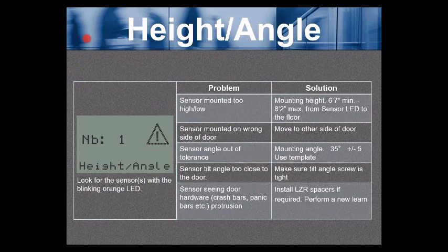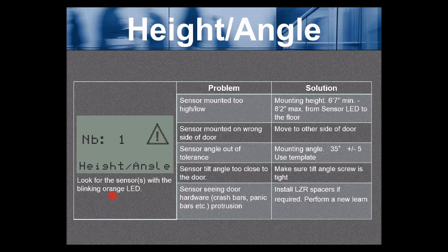Height angle error. Again, look for the sensor or sensors with the blinking orange LED. The problem for the height angle error, the sensor is mounted too high or too low. That's probably the number one cause of a height angle error. The mounting height is 6'7" minimum to 8'2" maximum from the sensor LED to the floor.